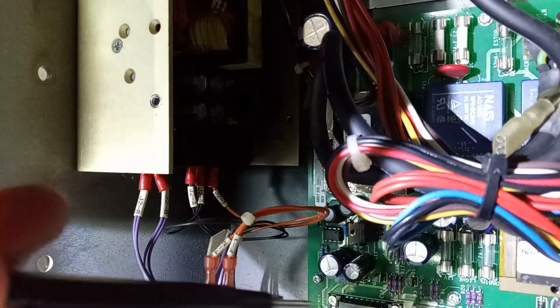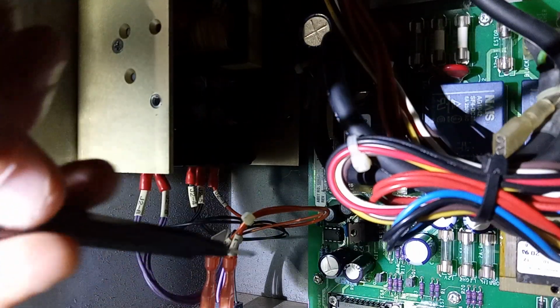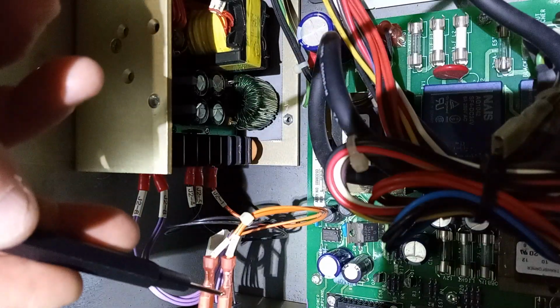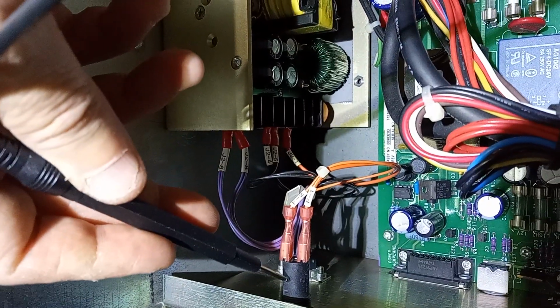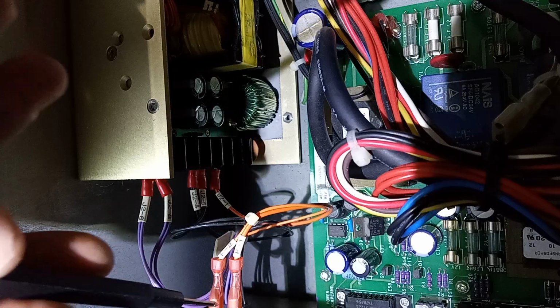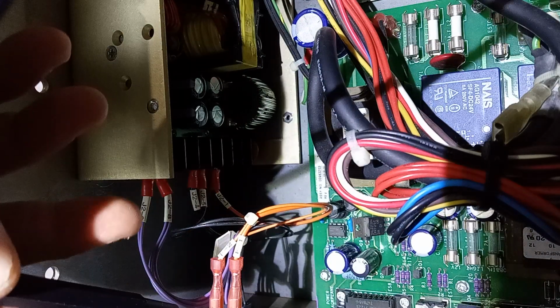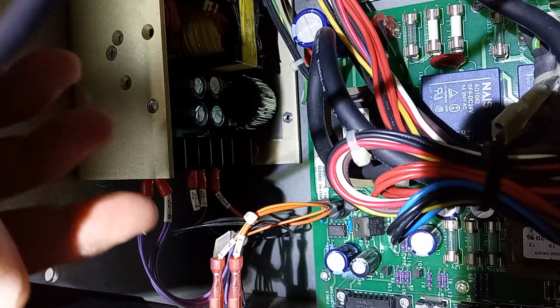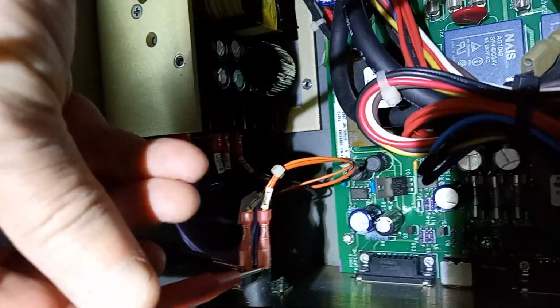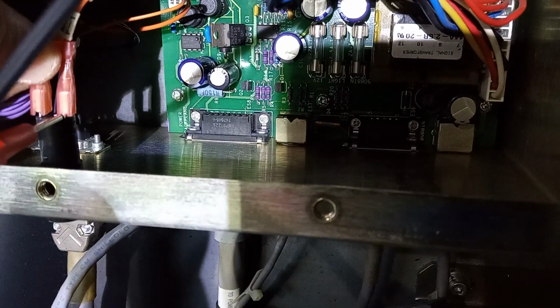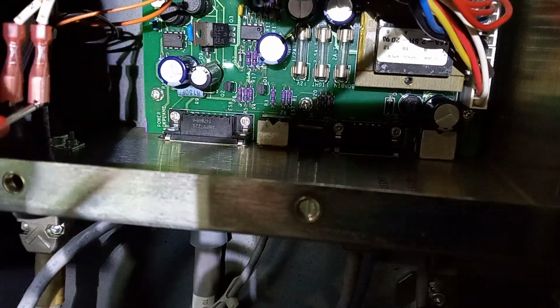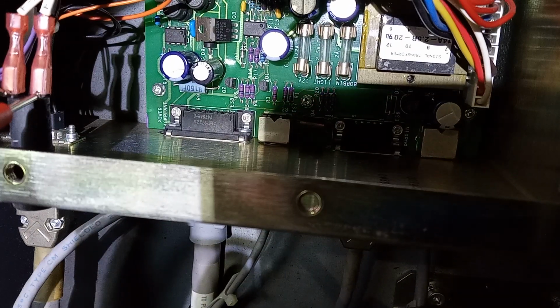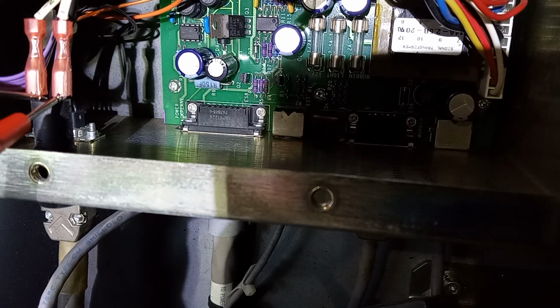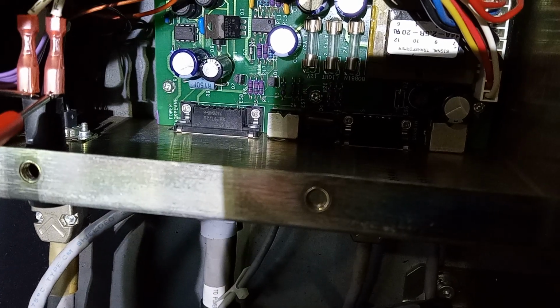So all 7 fuses are good. Oh, and this last one on the top right, which has the 2 orange wires, there's a fuse there. I believe that one's the 30 - I can't remember if that's the 24 or 36 volt line. But when you go across these two here, it should also give you continuity. You might have to poke that a little bit, or slightly take these 2 connectors out so you can get to the connector - there and there. See? That gives me good continuity, so that tells me the fuse is good.